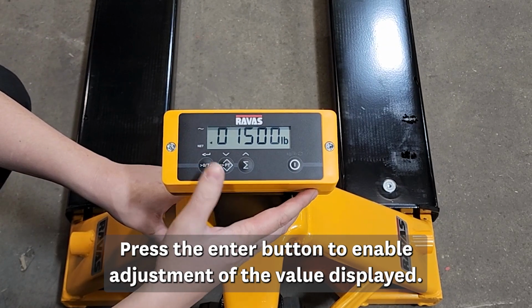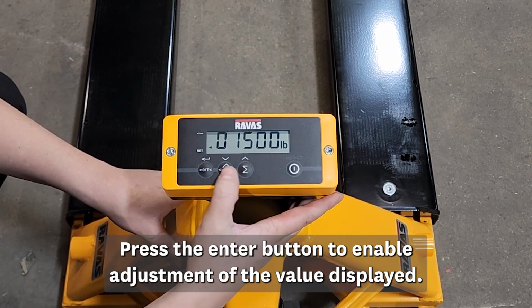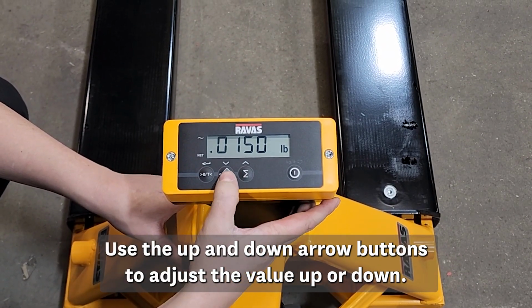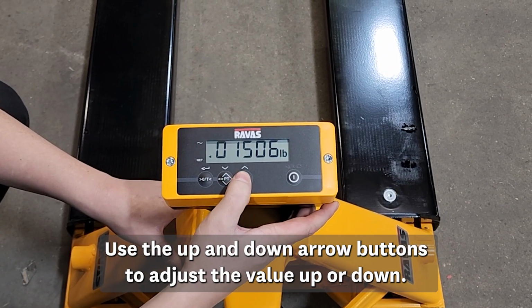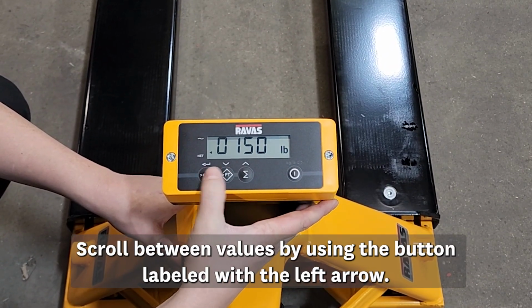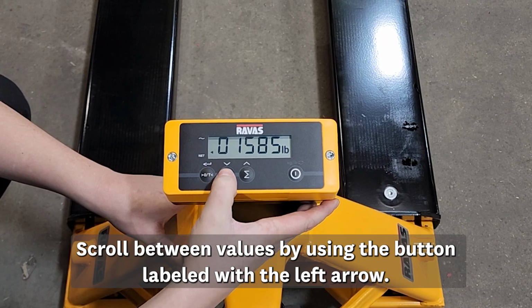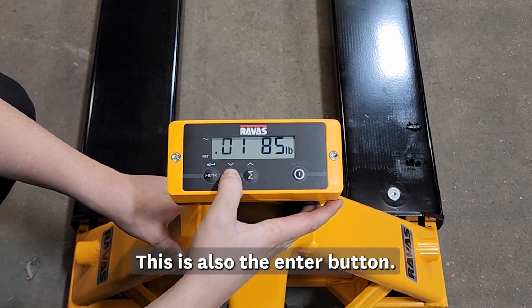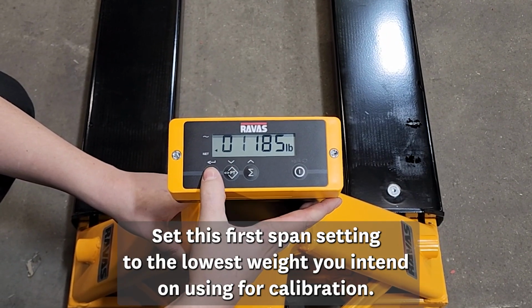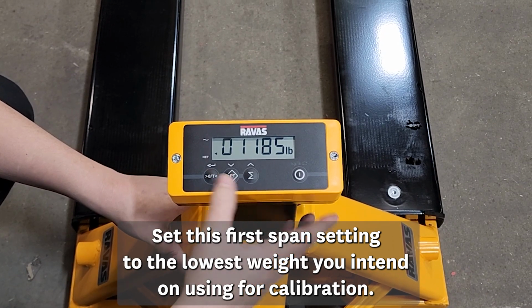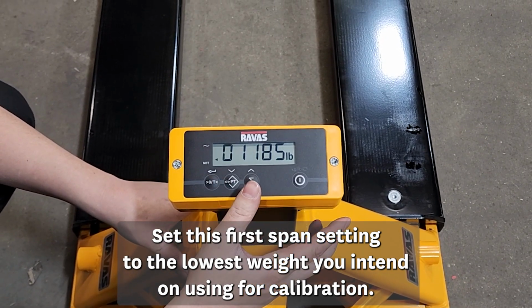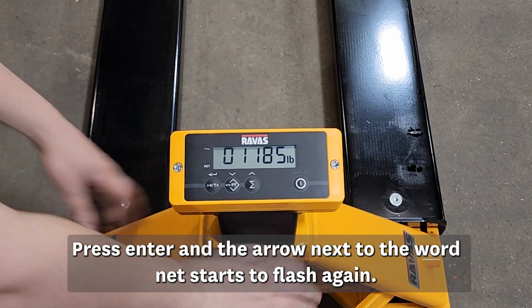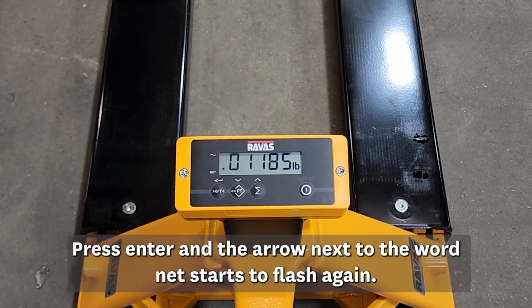Press the Enter button to enable adjustment of the value displayed. Use the up and down arrow buttons to adjust the value up or down. Scroll between values by using the button labeled with the left arrow. This is also the Enter button. Set this first span setting to the lowest weight you intend on using for calibration. Press Enter and the arrow next to the word net starts to flash again.